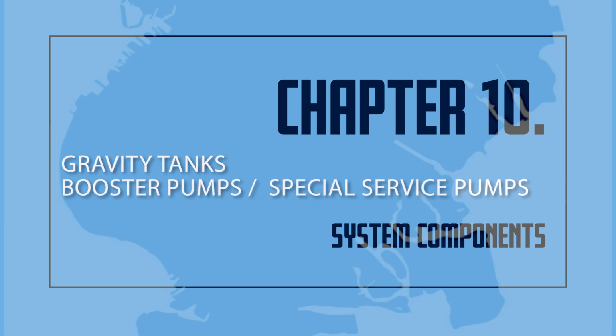Booster pumps/special service pumps. Booster pumps are sometimes used in sprinkler systems. These small pumps with limited power are usually located in the basement or taking suction from gravity tanks. The booster pump is used when the water pressure available at the highest sprinkler head does not quite meet the needs of the sprinkler system. This small pump increases the water pressure in the sprinkler system until it reaches acceptable levels. The booster pump should not be confused with the fire pump or the jockey pump.